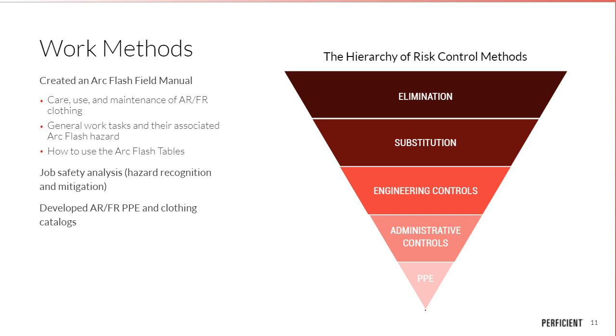So if you see on the right, there's a hierarchy of risk control methods. This is a concept that initiated in Europe a few years ago, and then it was imported to the United States through the NFPA 70E. And it has a good approach in which you start with an evaluation of hazards present, the risk, or in that case, how much they can occur, and then how intensive they are in terms of potential to produce harm.